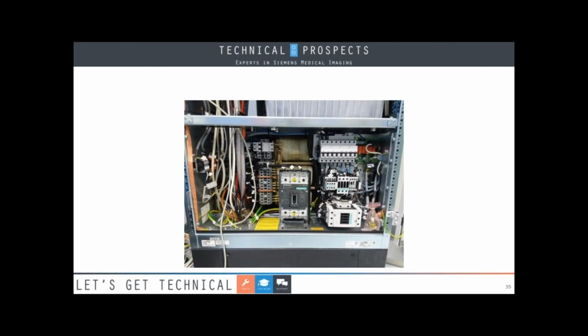We'll go a little bit over power issues. This is just a typical fluoroscopy table power cabinet. When the system's off, but the breaker's on, you should have power to a detector, or if it's an older system, an image intensifier. You should also have power going to your control box, so when the operator presses the on button, the system boots up.